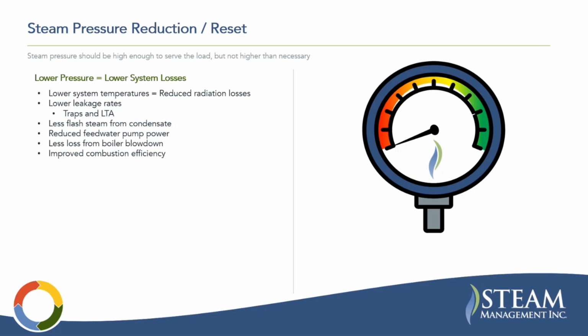Steam pressure reduction and reset. Basically the idea here is steam systems are best operated at their lowest pressure required. So you want to be high enough to serve all of your loads and not cause any issues, but there's no benefit of operating higher than necessary. And the lower the pressure of the steam system, the less the losses are.